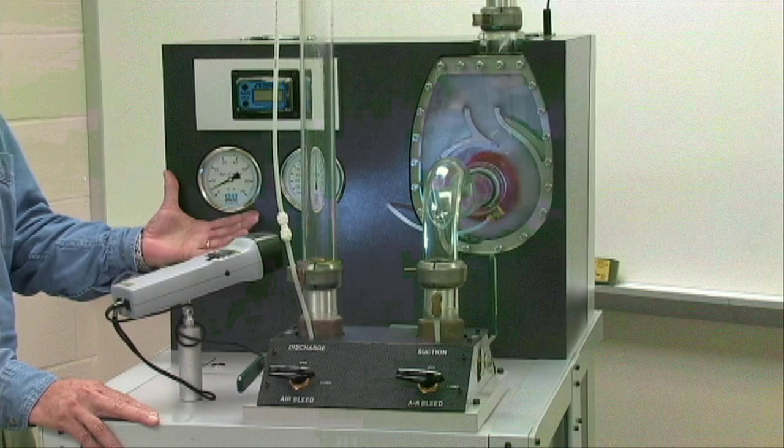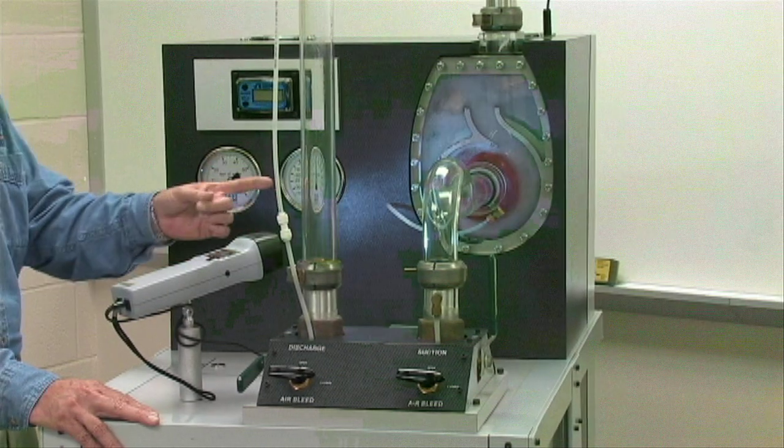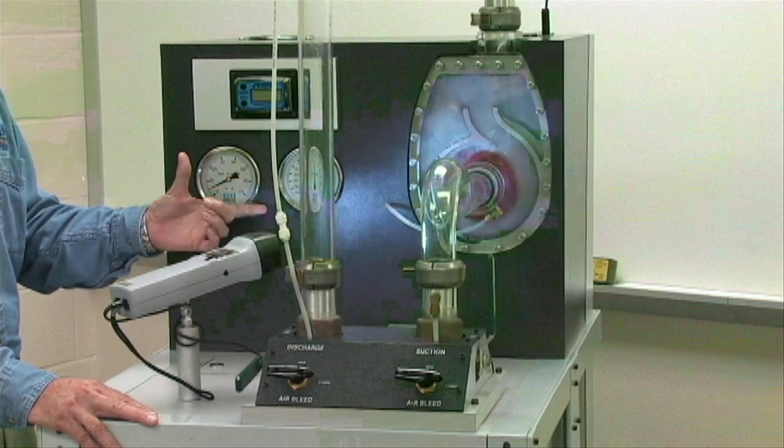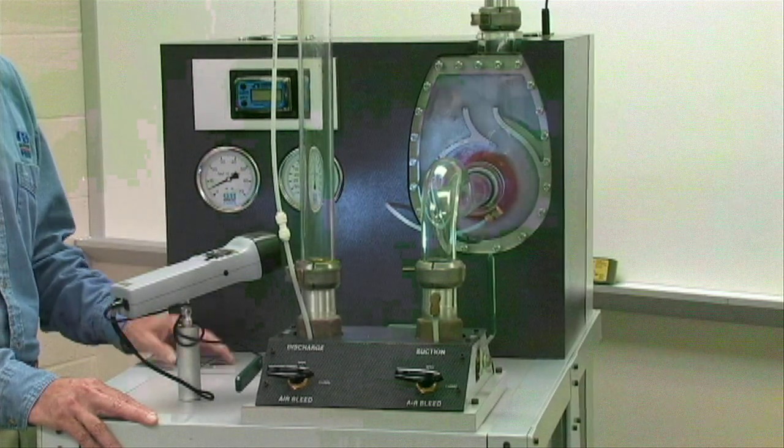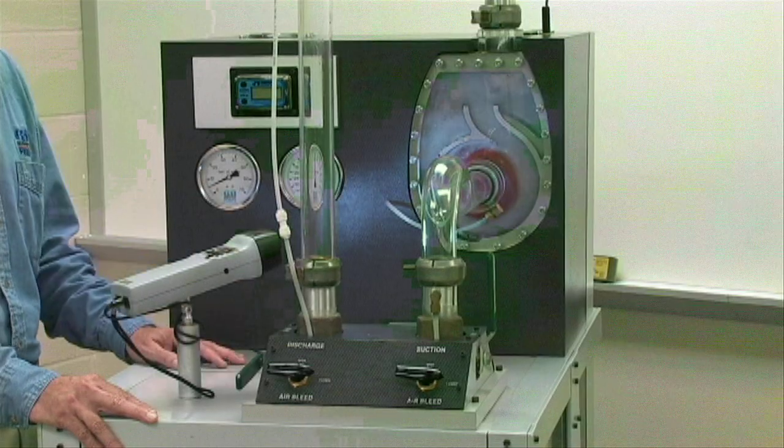Noting the pressure on the discharge gauge during the priming process proves that air is being compressed on the discharge side, not allowing water to move up the suction pipe.